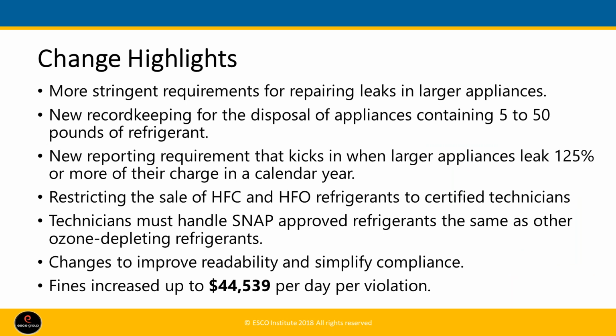The majority of the regulatory changes that have occurred involve the maximum annual leak rates, leak testing, and record-keeping requirements. Affecting most of the industry is the new record-keeping for the disposal of appliances containing 5 to 50 pounds of refrigerants. This is a new one that affects just about all the contractors. There are more stringent requirements for repairing leaks in larger appliances, with a new reporting requirement that kicks in when larger appliances leak 125% or more of their charge in a calendar year.